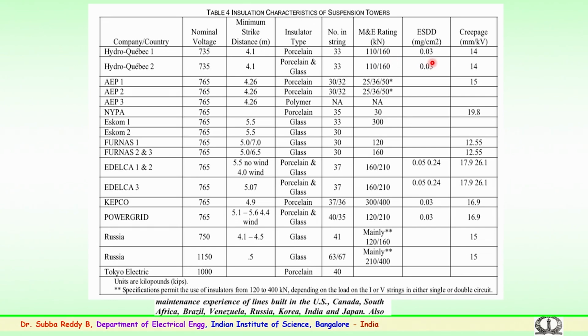Then the column shows the ESDD, equivalent salt deposit density, for when transmission lines are running near pollution zones. For those particular pollution zones, the equivalent salt deposit density being used has also been categorized here. Then the final column gives the creepage in millimeters per kV adopted for the insulators. That is, 14 mm per kV is the adopted creepage. You can see various companies in different countries, the voltage levels adopted, 735, 765, and the minimum strike distance, what type of insulators are used, how many insulators are employed in a string, the mechanical rating, the pollution conditions and the creepage employed.